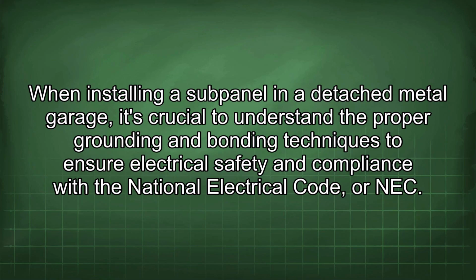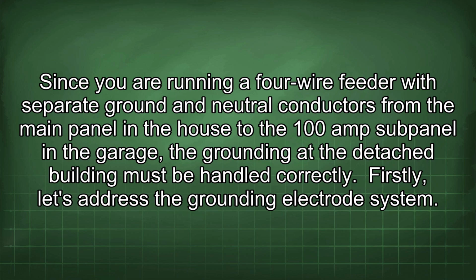When installing a subpanel in a detached metal garage, it's crucial to understand the proper grounding and bonding techniques to ensure electrical safety and compliance with the National Electrical Code, or NEC. Since you are running a 4-wire feeder with separate ground and neutral conductors from the main panel in the house to the 100 amp subpanel in the garage, the grounding at the detached building must be handled correctly.